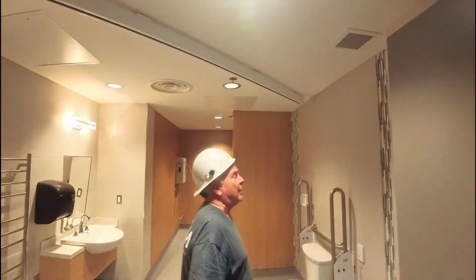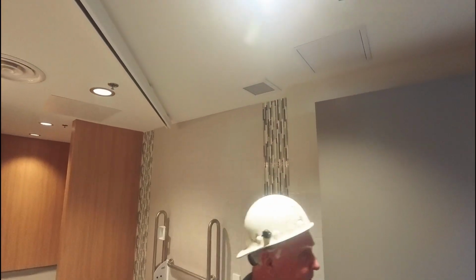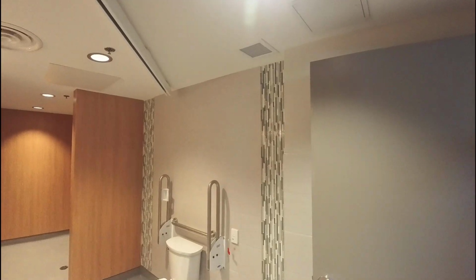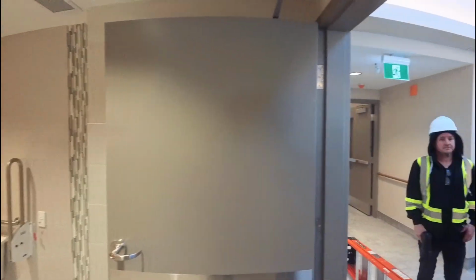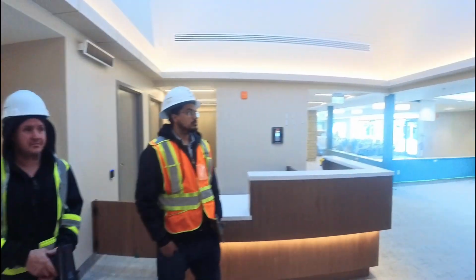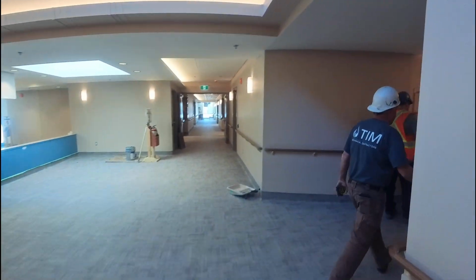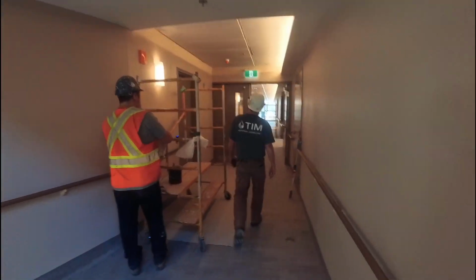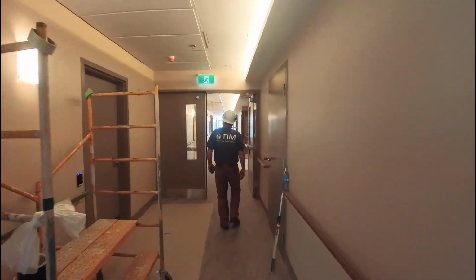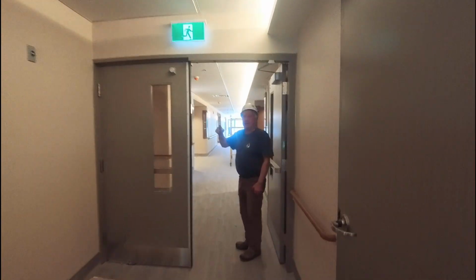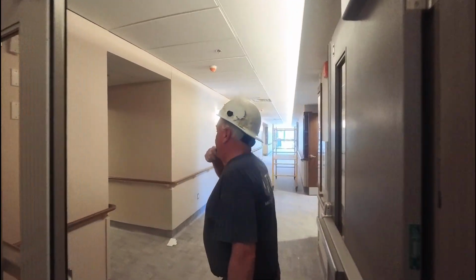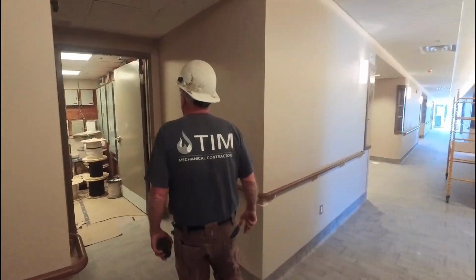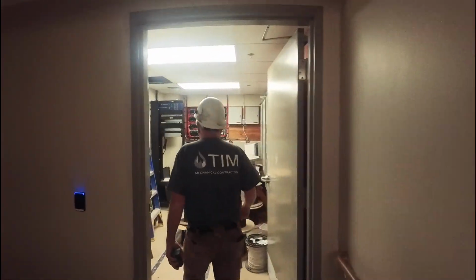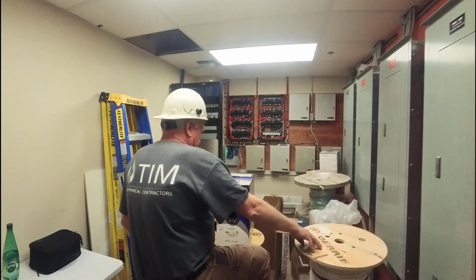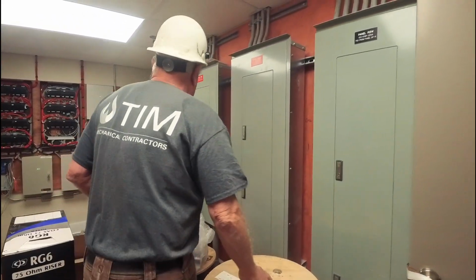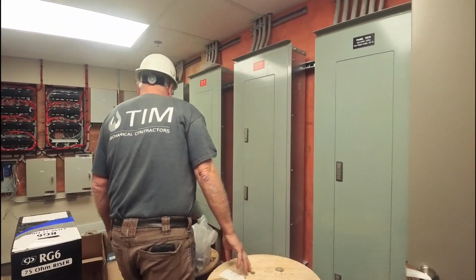Besides being totally loud, and you know why it's loud? It's because the dampers are probably off again. It's not supposed to be that loud? No. Not that loud. Because they've been going around changing that sensor for the smoke detector, right? And he's been shutting the fire dampers off. And the unit's running.